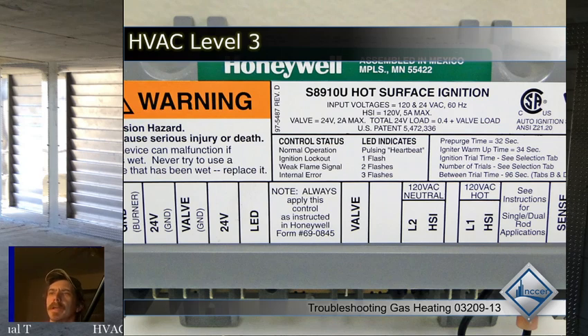Got a troubleshooting guide. Okay, yeah, if you look through the troubleshooting guides, I got a system evaluation guide there. That is pretty good at looking at a sequence. It's not perfect, but that's pretty good. I'll try and post the worksheet that has my version of that refrigeration troubleshooting guide on it. But anyway, remember that in a heat pump, the roles can get reversed, right? So normally your system is in cooling. The outdoor unit will have hot vapor at the beginning, and at the end have a subcooled liquid. And your indoor unit will have a subcooled liquid at the beginning and a superheated vapor at the end, right?